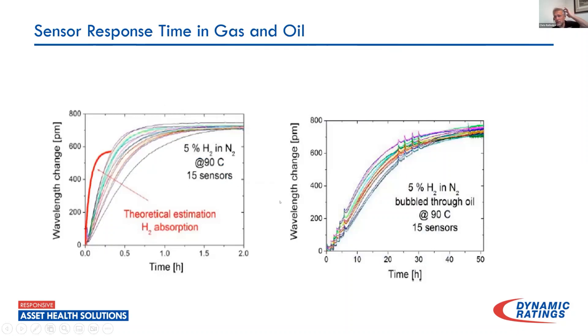Data provided by a sensor manufacturer testing hydrogen sensors shows on the left — hydrogen in nitrogen versus hydrogen sparging through oil. They reached the total hydrogen level in about an hour when in gas. However, when sparging through oil with the same 15-sensor setup, it was greater than 50 hours to reach that total. It definitely affects the response time of the sensor considerably.